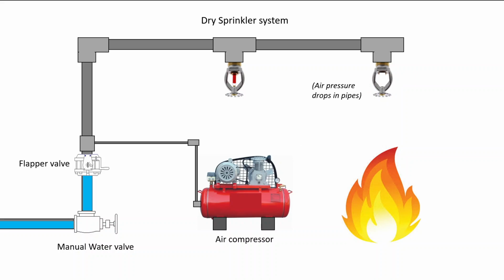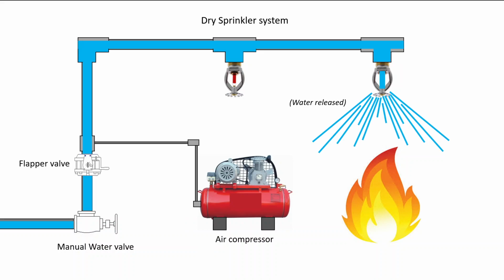Now, the air pressure will drop in the pipes, and depending on the size and the capacity and the design of the system, the air compressor might be controlled in such a way that it has power cut off to it, in which case the pressure drops much quicker. Other systems, the air compressor can just simply not keep up with the pressure drop. In either situation, what will happen is that this dry section, pressure-wise, will drop, and that will cause the flapper valve to then open. Water will then fill the sprinkler pipe and flood through to the open head where it will be released on the fire.